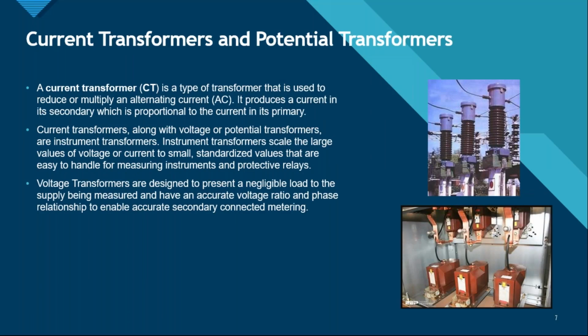Then there can be current transformers and potential transformers. Now current transformers can be at two different locations. One can be outside near your power transformer. That will be on the supply side, right? The top photo that you see over here is outside in the substations. Those are the current transformers, three transformers for three phases, red, yellow, and blue, right? And the bottom one that you see, in the bottom also you can see six in total red structures. The three on the top are the current transformers, and the three on the bottom are potential transformers.